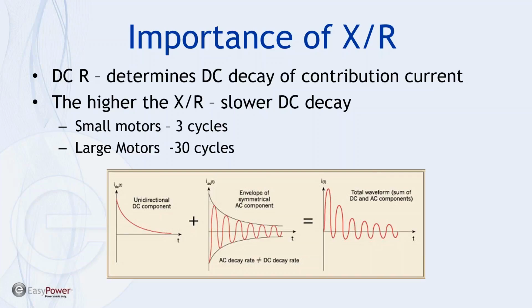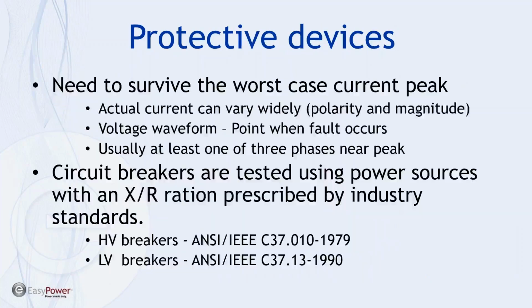Now, why do we care about all this? Well, again, this is the worst case situation that the system will ever see, and for it to be able to withstand this surge or these peaks of current, we need to comprehend this factor into our design and selection of protective devices. And so since they need to survive the worst case, we need to make sure we're talking apples and apples when it comes to the way they've been tested in the factory compared to the way they're going to be applied in our application.